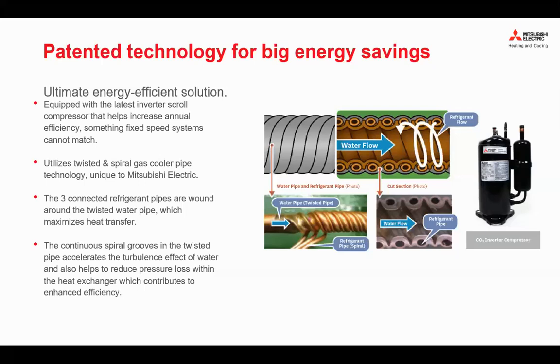On top of that, Mitsubishi introduced this unit equipped with a twisted spiral gas cooler pipe. You can see the water is flowing in the middle of the pipe, and around the water piping there is a section of twisted, spiral refrigerant piping. This increases the surface area, which increases the rate of heat transfer, and therefore increases the efficiency of the unit. As you can see, there are 3 contacting surfaces. That's why it was able to reach that efficiency just by increasing the surface area. We also like to have turbulent flow, so the heat is properly transferred between the water and the refrigerant throughout the unit.